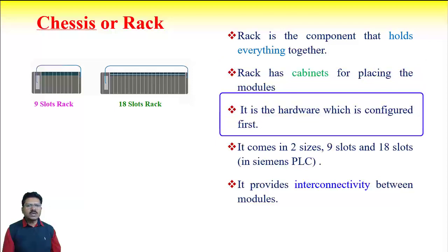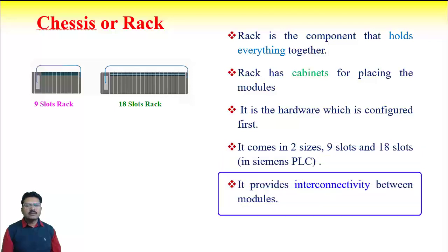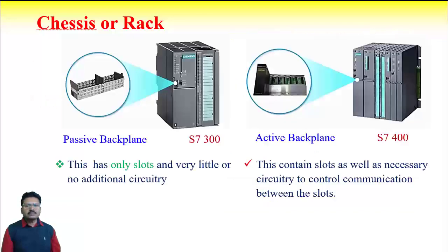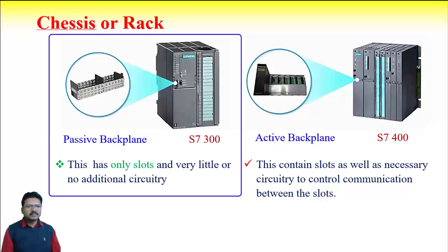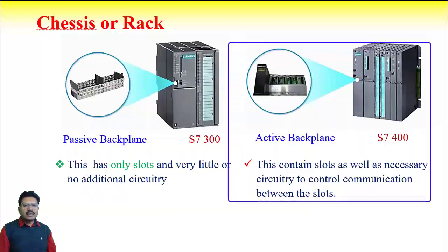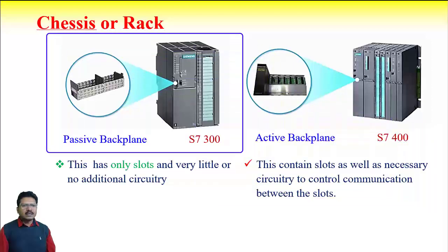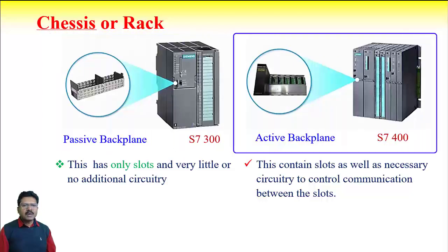At the start of PLC use we must configure the hardware, and the rack is normally configured first. In Siemens PLC it comes in two sizes: 9 slots and 18 slots. The rack or chassis provides interconnectivity between different modules. There are mainly two types of racks: passive backplane and active backplane. A passive backplane has only slots with very little or no additional circuitry, whereas an active backplane contains slots as well as necessary circuitry to control communications between the slots. For example, the S7300 has a passive backplane chassis and the S7400 has an active backplane chassis.